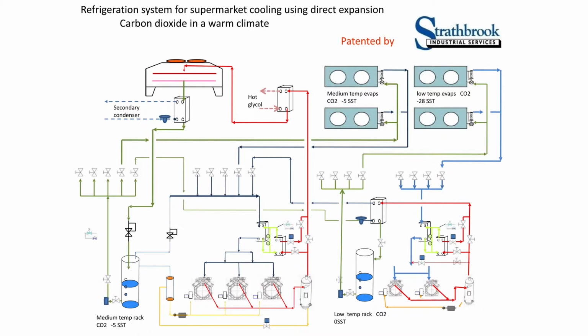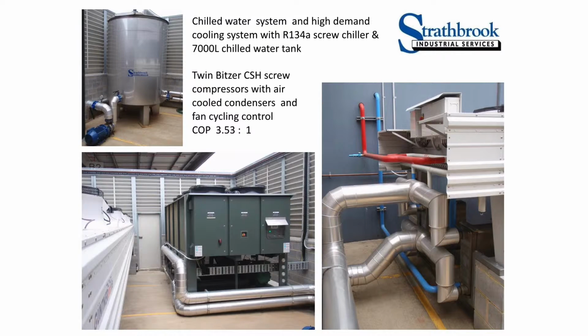So to keep our CO2 system cool, we basically added in a plate heat exchanger on the outlet of the heat rejection condenser, and we put a second cooling system on that, so that on a hot day this second cooling system turns on. We cool the CO2 coming out of the condenser to make the plant think that it's a cold day. We maintain the energy efficiency, albeit by burning some extra energy to run this chiller, but the chiller's running at a much higher suction pressure, so it in itself is much more energy efficient. And the chiller looked like that.